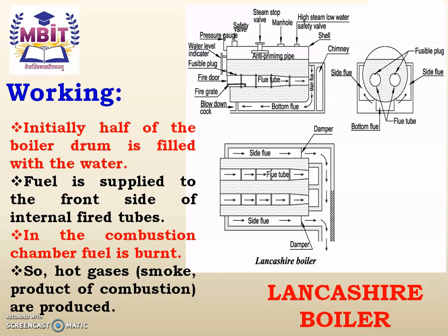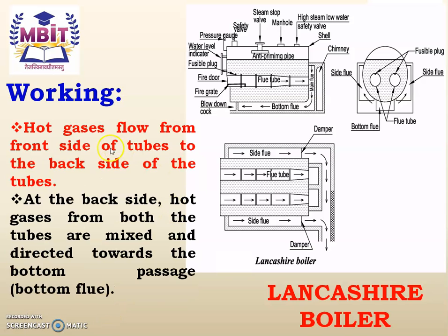Now let us study the working of the boiler. Initially, half of the boiler drum is filled up with water. Fuel is supplied to the fire grate at the front side of the two internal fire tubes. The fuel is burned in the combustion chamber, and hot gases — also known as smoke or products of combustion — are produced. These hot gases flow from the front side of the tubes to the back side of the tubes.